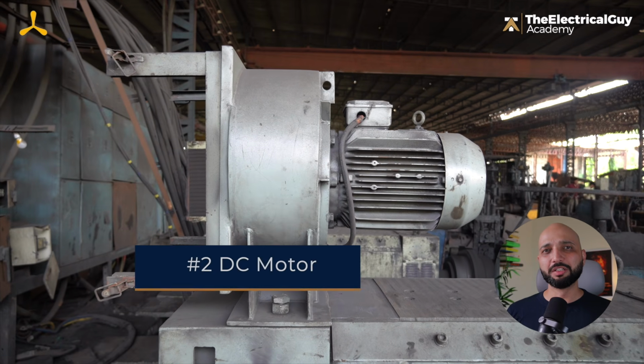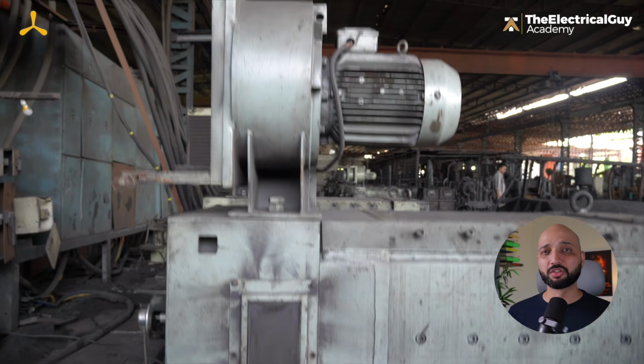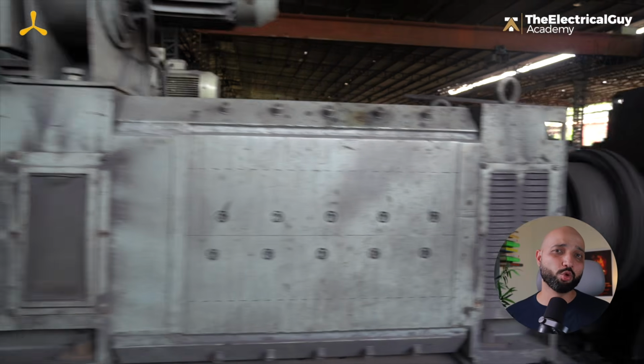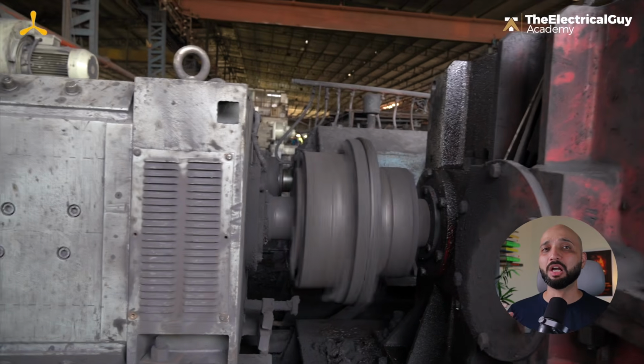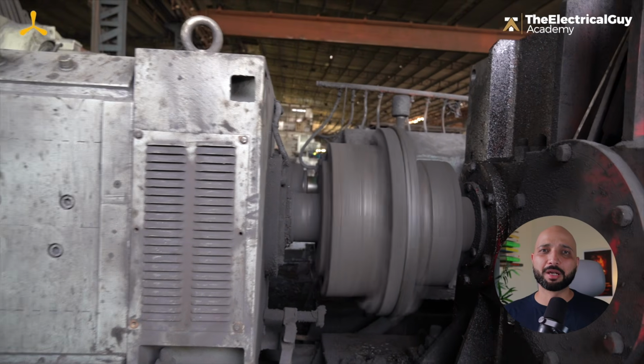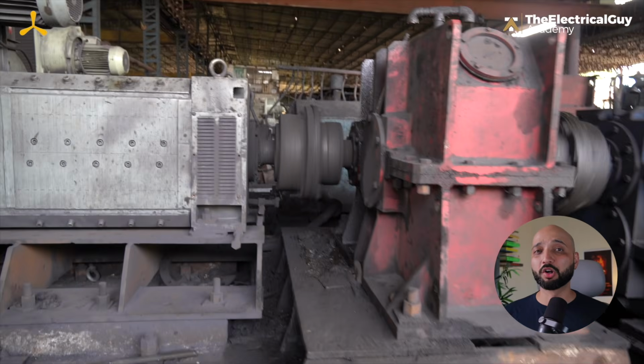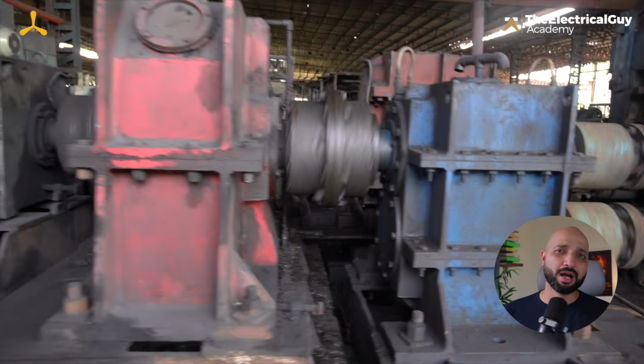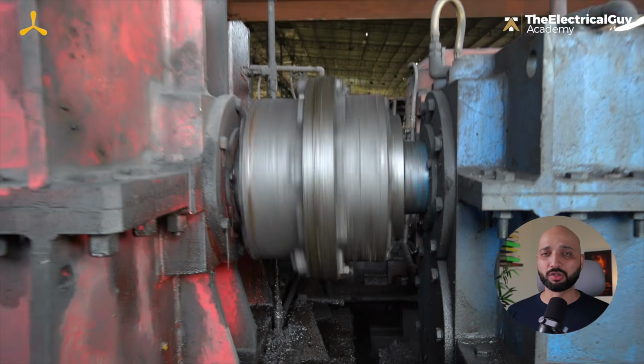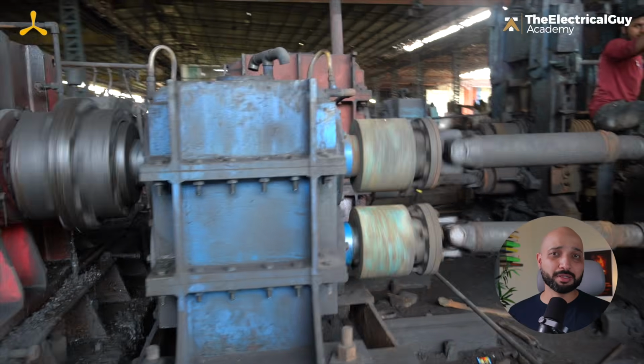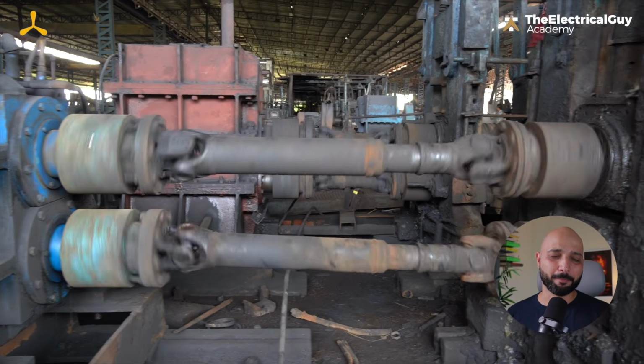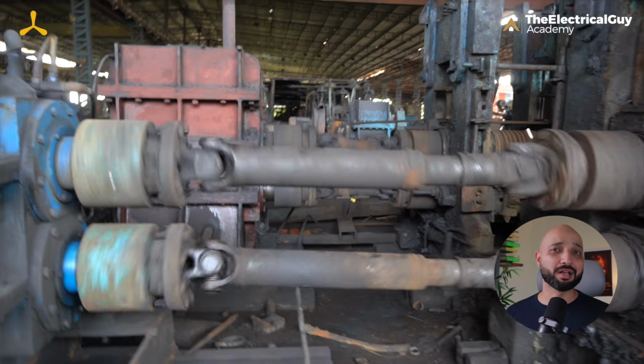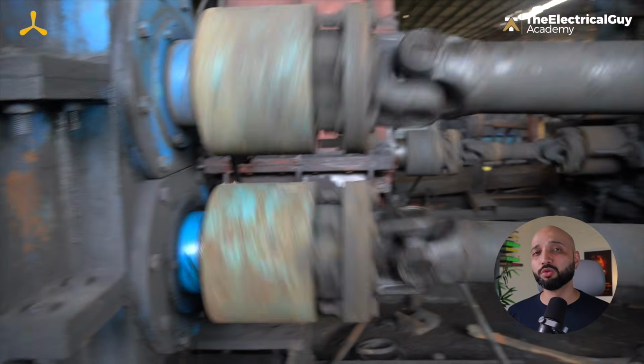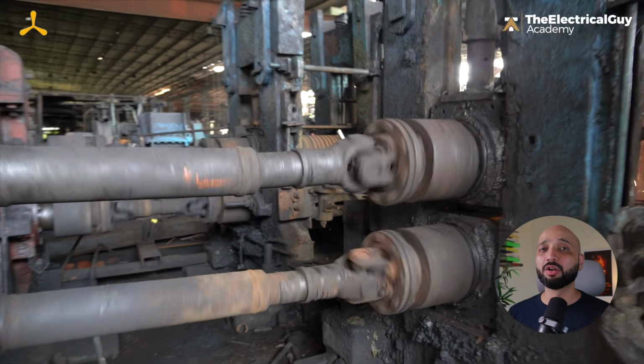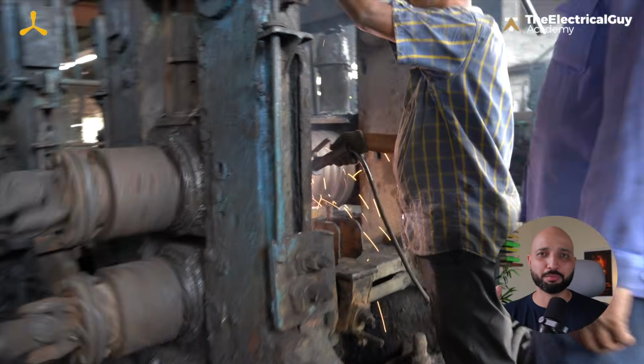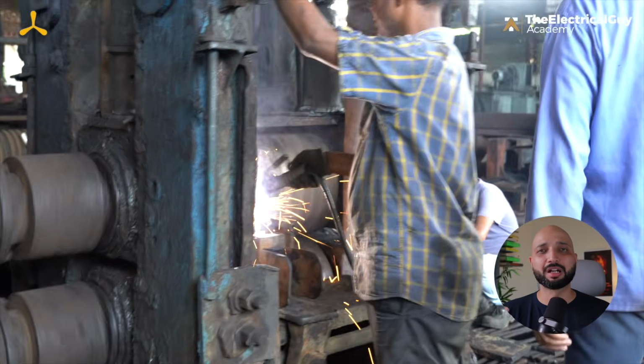Now let's talk about the DC motor in rolling mills. Historically and still in many existing mill lines, DC motors have been the industry benchmark for steel rolling application. Before AC drives became so advanced, DC motors were preferred because they offered excellent speed control, high torque at low speed, smooth operation, and fast response. In rolling mills, these qualities are very important. A DC motor can provide high torque even at zero speed. It can handle smooth low speed operations. And its speed torque control is almost linear, which makes it very useful where accurate speed control is required.